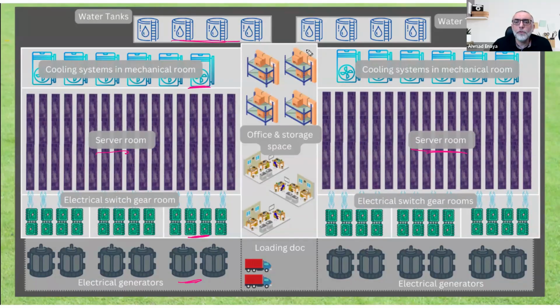Do you want to have both rooms connected to the same cooling system? No. Do you want both to have the same set of generators? No, they should be totally independent. If a total disaster happens and this room is fully down, whatever happens here doesn't affect the other one. This is within the same building.